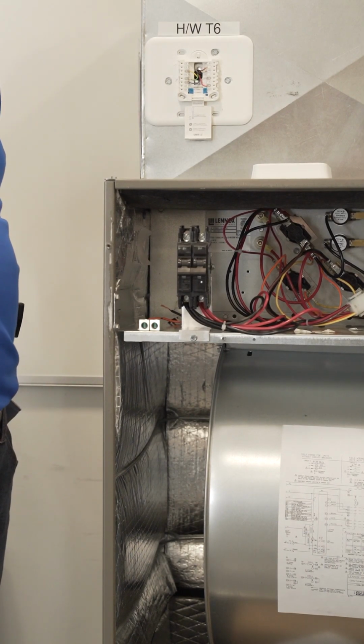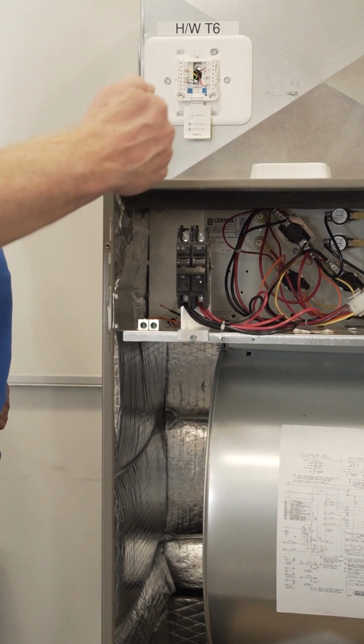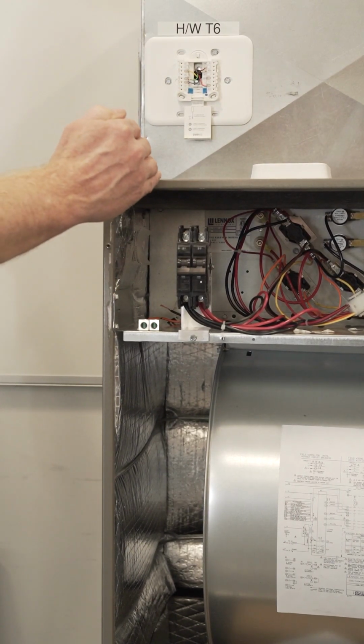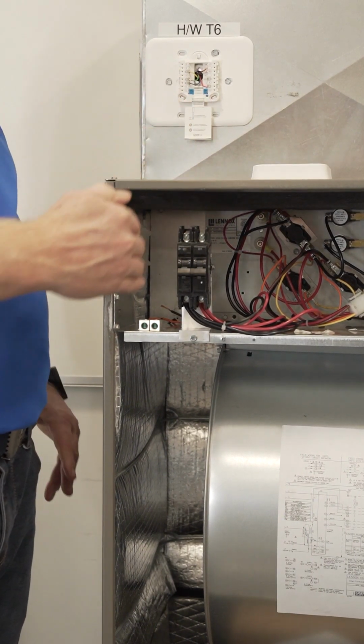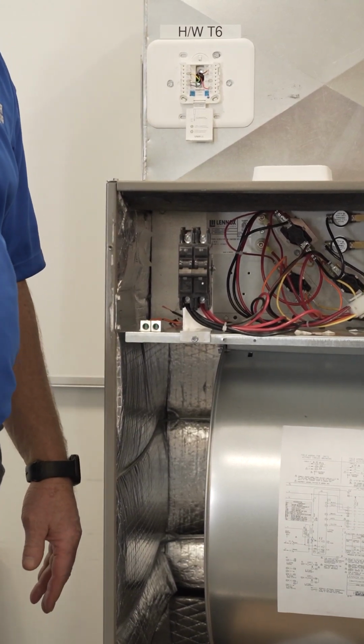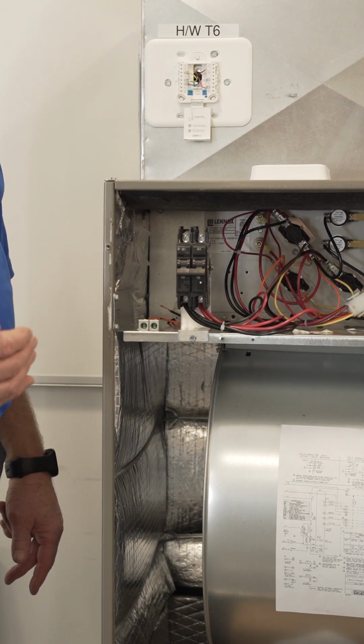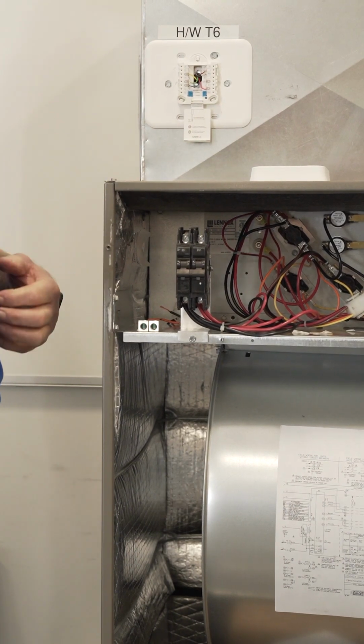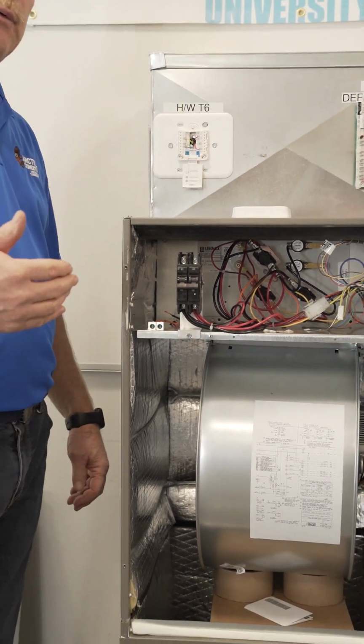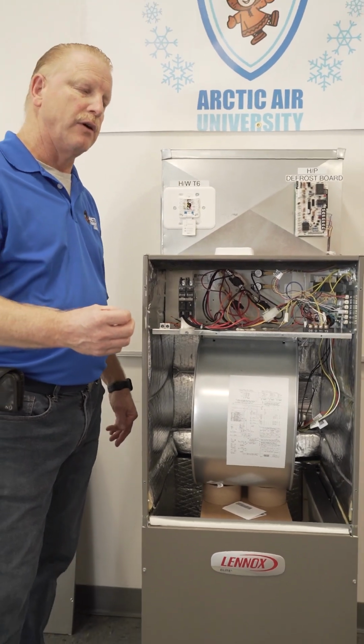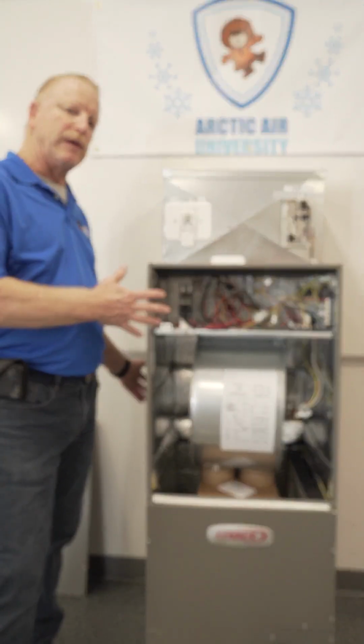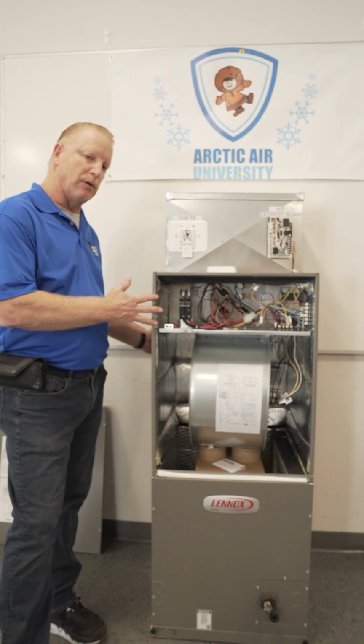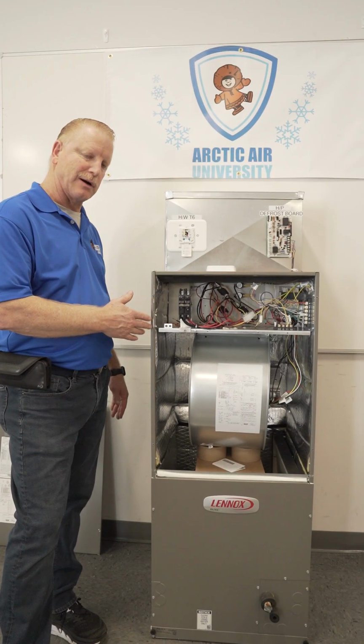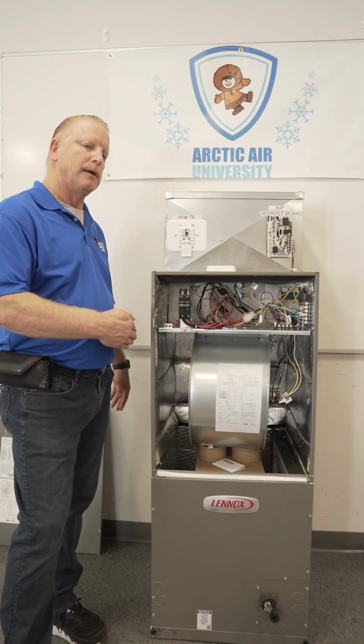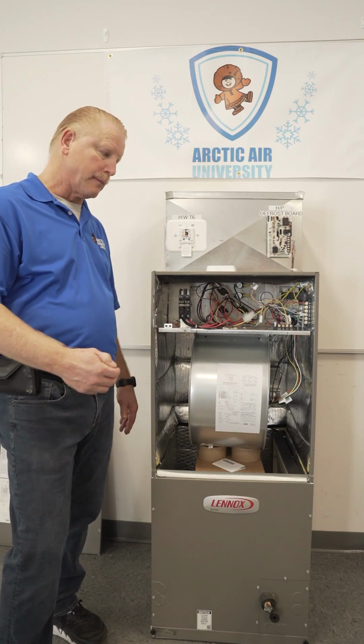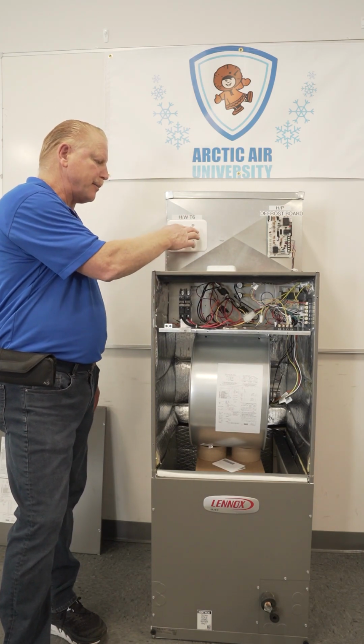Depending on what equipment you are installing is how you program the thermostat. Do I want the thermostat to energize the reversing valve for cooling, or do I want to energize it for heating? Our Lennox units, you always program it for O, so we energize the reversing valve for cooling. So we fail in heating mode. If that reversing valve does not work for a Lennox piece of equipment, it is always on and heating. All right, button this back up.